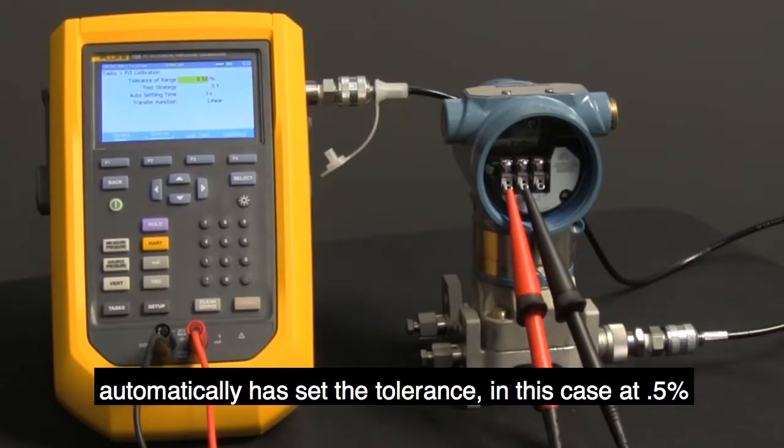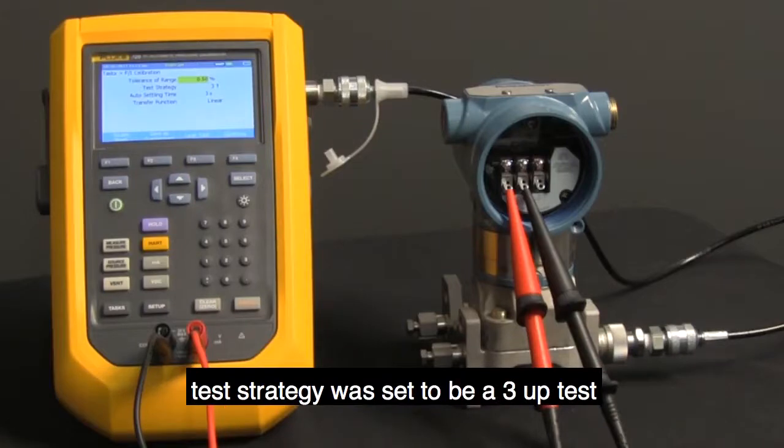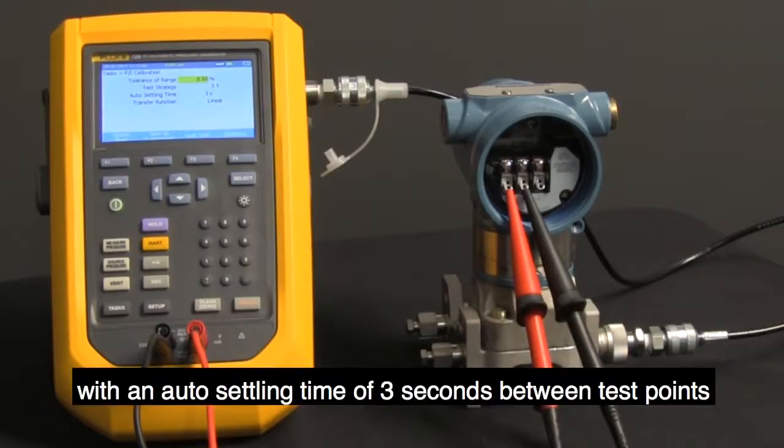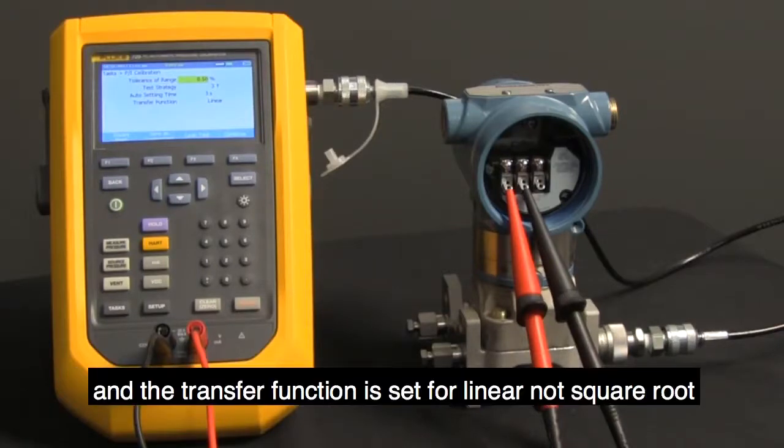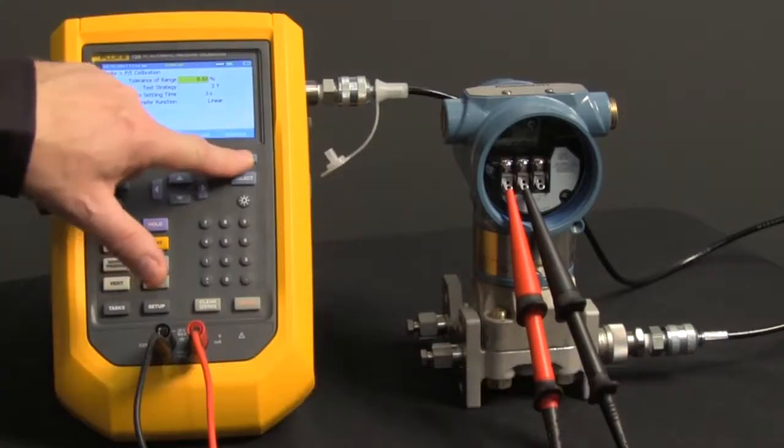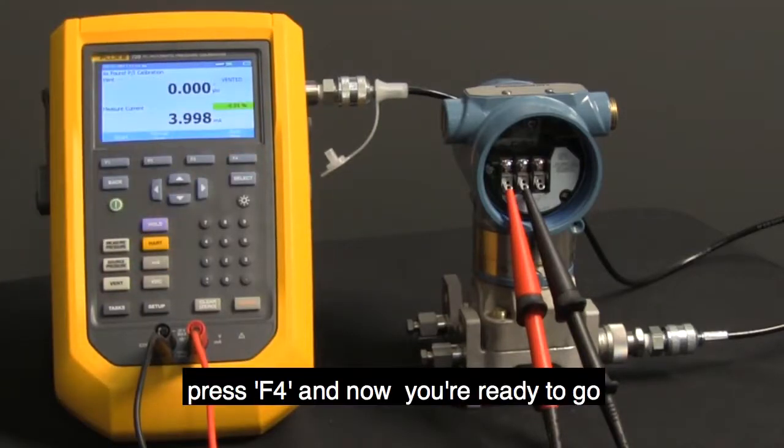Automatically has set the tolerance in this case at 0.5%. Test strategy was set to be a three up test with an auto settling time of three seconds between test points. And the transfer function is set for linear, not square root. Press F4 and now you're ready to go.